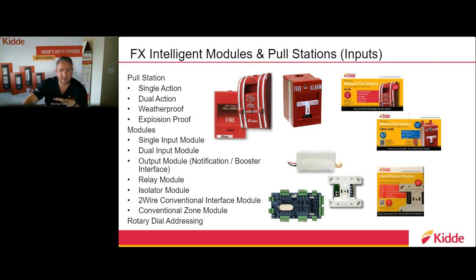Looking back at the addressable side, we have our module types: single input, dual input, and output modules that supervise and sync our output circuits for our booster power supplies. We also have your run-of-the-mill relays, isolator modules, and a 2-wire conventional interface module that can hold up to 18 module addresses on the panel and tie in 16 conventional inputs.